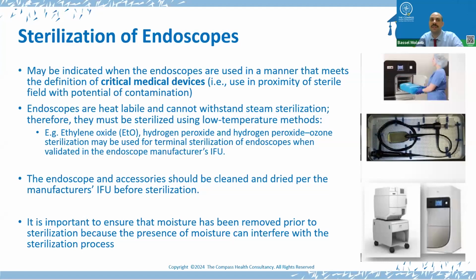Therefore, they must be sterilized using low temperature methods, for example, ethylene oxide or hydrogen peroxide or ozone sterilization as a means for terminal sterilization. And this should be validated as per the IFUs. And the scope and its accessories should be cleaned and dried per manufacturer's IFUs before the sterilization. And it is important to ensure that the moisture has been removed prior to sterilization, because presence of such moisture in the lumens may interfere with the sterilization process.